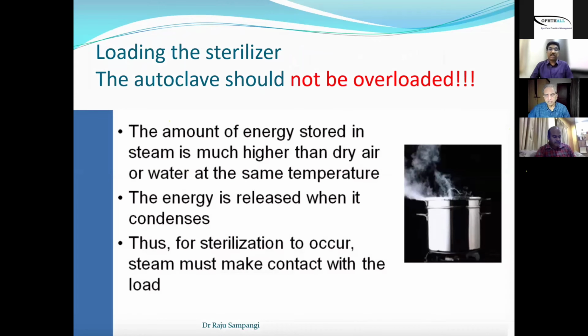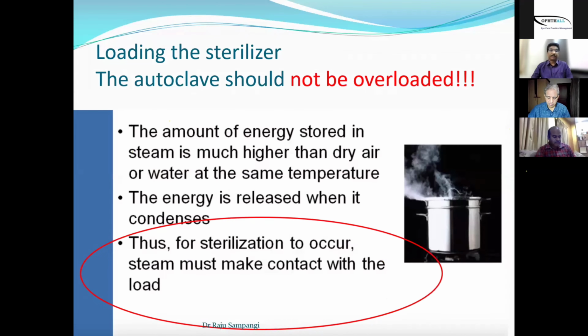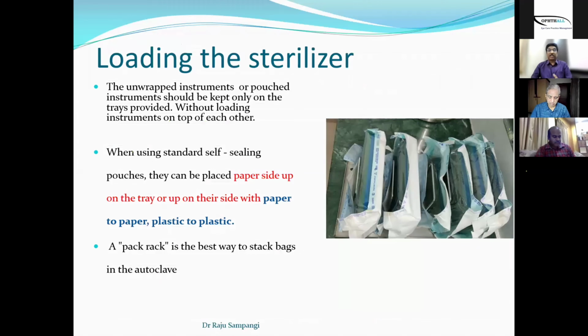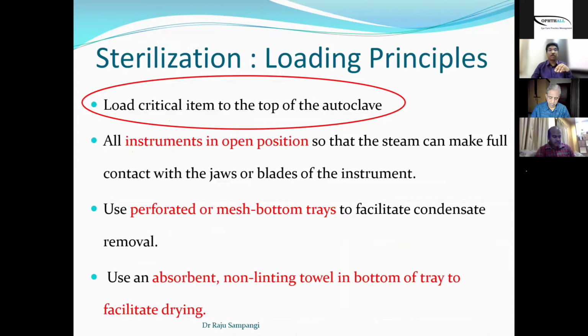Then loading the sterilizer. The sterilizer should never be overloaded. You should never overload your sterilizer. You should have spaces in between so that the steam can go through it. This is one of the ways where you can load the sterilizer: pack them, and neatly arrange them in such kind of trays so that the steam penetration will be equivalent and it can penetrate from all directions, which means the surface area for contact of steam is more.